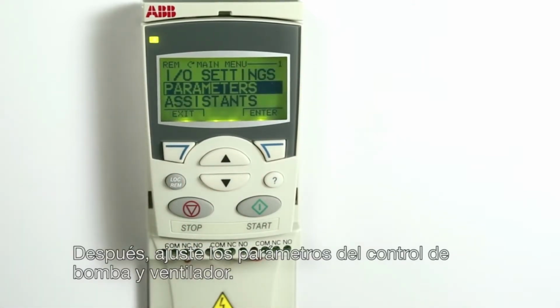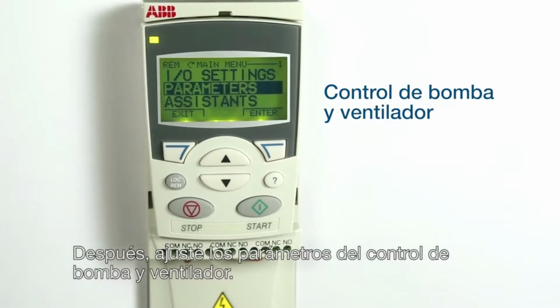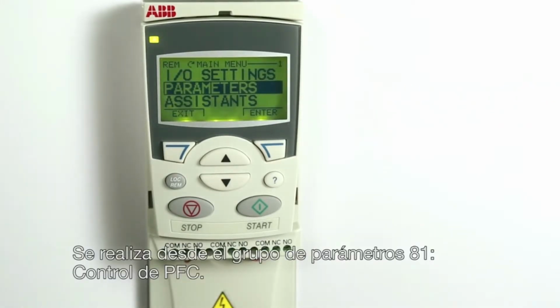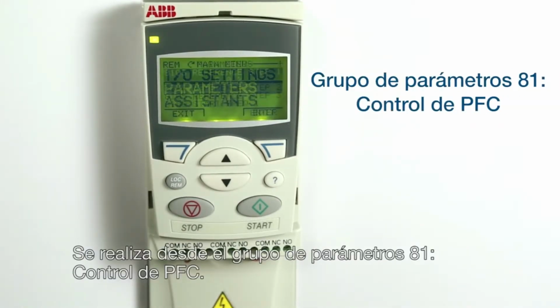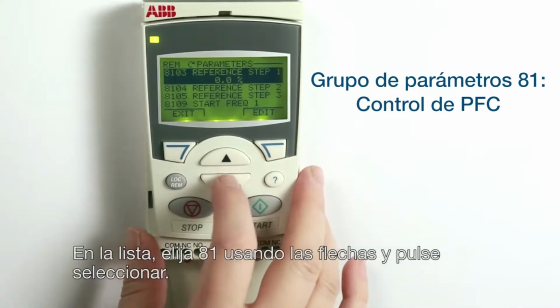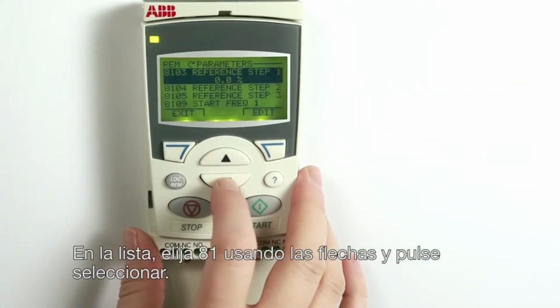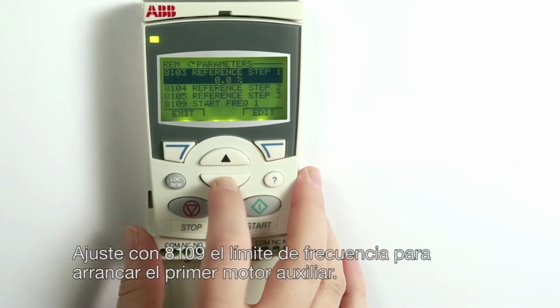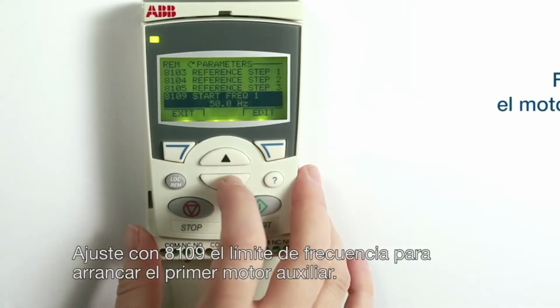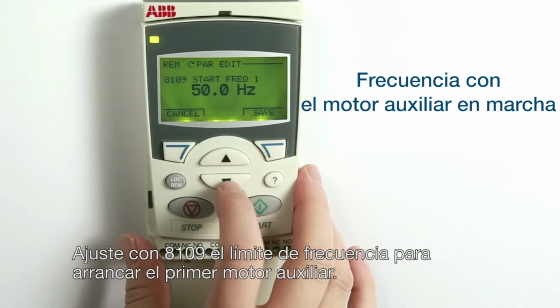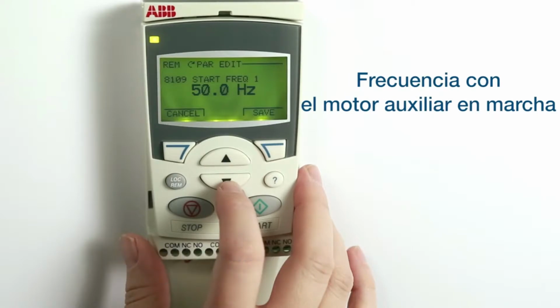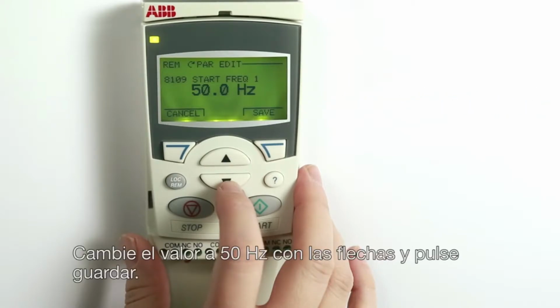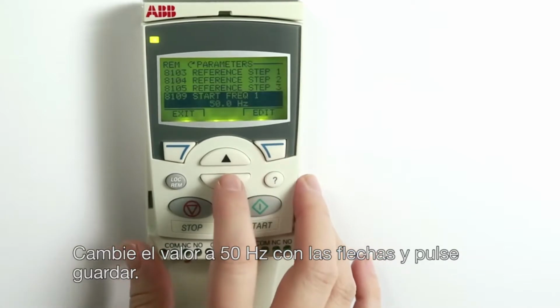Then we configure the parameters for pump and fan control. This is done from parameter group 81, PFC Control. Choose the 81 from the list using arrow keys and press Select. First, we set the frequency limit used to start the first auxiliary motor from parameter 8109. So change the value to 50 Hz with arrow keys and press Save.